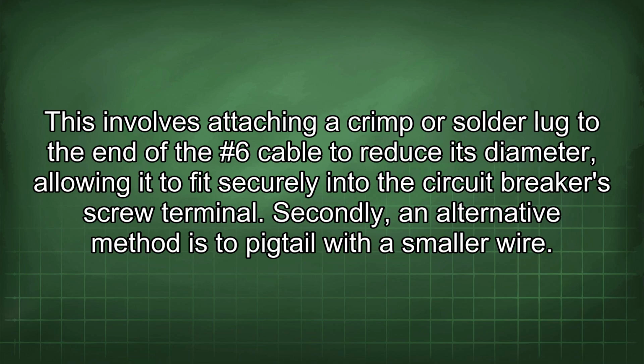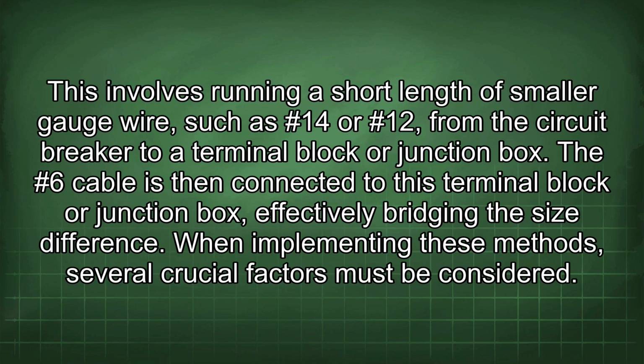Secondly, an alternative method is to pigtail with a smaller wire. This involves running a short length of smaller gauge wire, such as #14 or #12, from the circuit breaker to a terminal block or junction box. The #6 cable is then connected to this terminal block or junction box, effectively bridging the size difference.